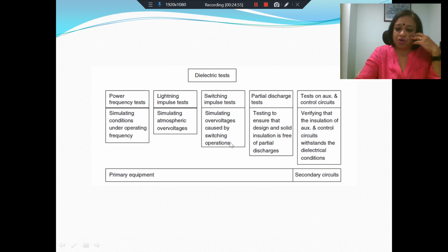simulating overvoltages caused by switching operations, PD test. There is a whole range of PD tests, and it also forms a part of the online condition monitoring of the system. These PD tests are done to ensure that the design and the solid insulation is free of partial discharges at all times. And then you would have tests on auxiliary and control circuits, which will verify that the insulation of the auxiliary and control circuits withstand dielectric conditions. This will be mainly done on secondary circuits, and all these first tests will be done on the primary equipment.